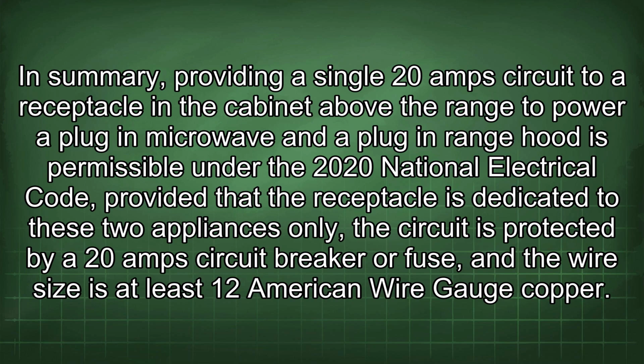In summary, providing a single 20-amp circuit to a receptacle in the cabinet above the range to power a plug-in microwave and a plug-in range hood is permissible under the 2020 National Electrical Code, provided that the receptacle is dedicated to these two appliances only. The circuit is protected by a 20-amp circuit breaker or fuse, and the wire size is at least 12 American wire gauge copper.